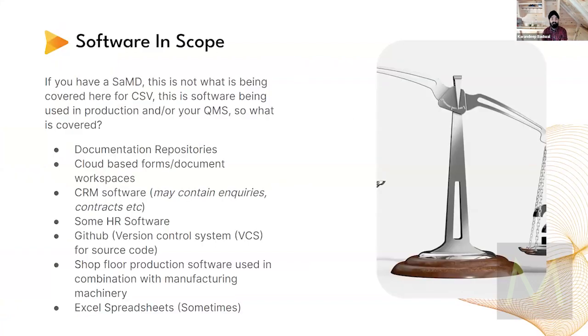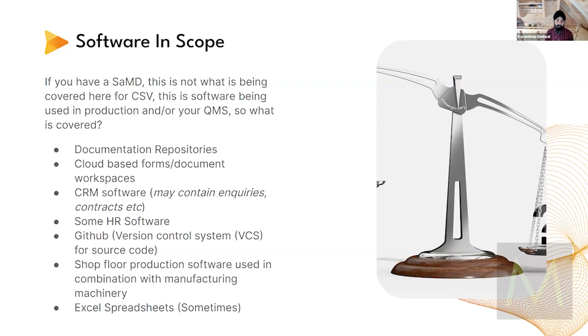Which software is in scope of software validation? If you have a software medical device — as Melissa mentioned earlier — that's not what we're covering here. This is software being used in the production and/or your quality management system. What's covered: document repositories — SharePoint, Google Drive, and internal servers. Where are you keeping your approved documentation, your draft documentation, your superseded documentation? That all needs to be validated. Cloud-based forms and document workspaces — if you're using cloud-based systems, those need to be validated.